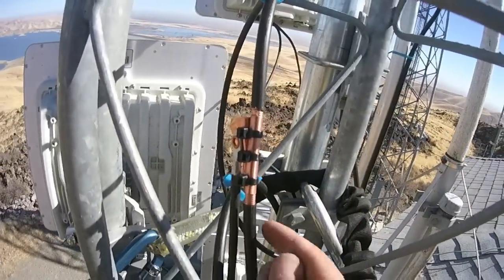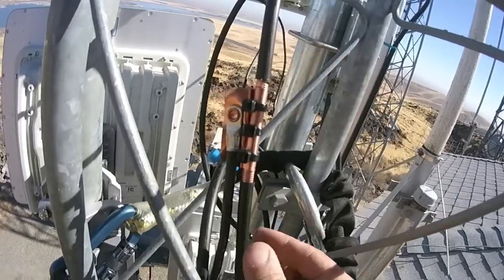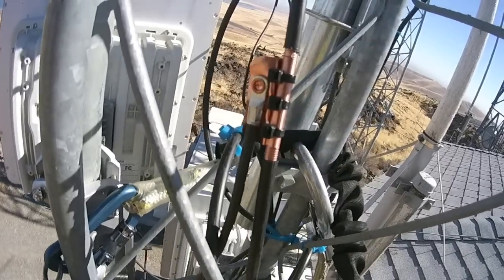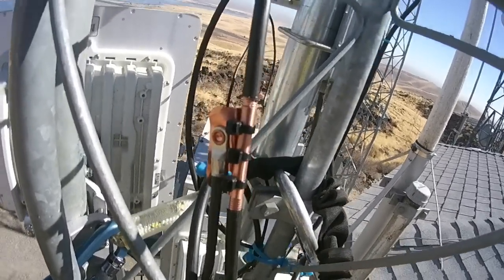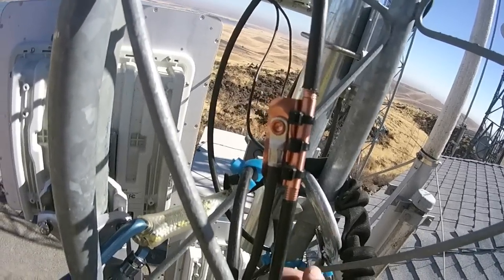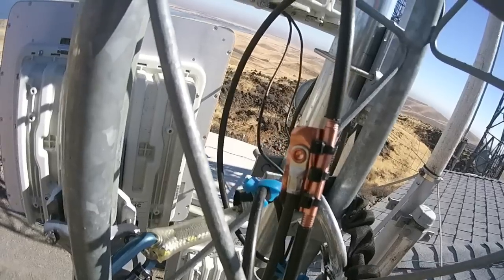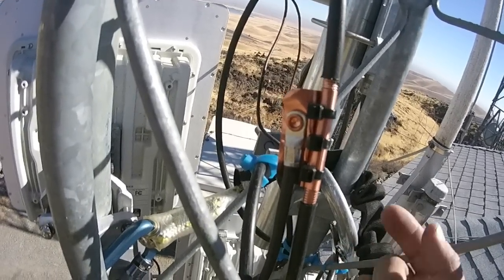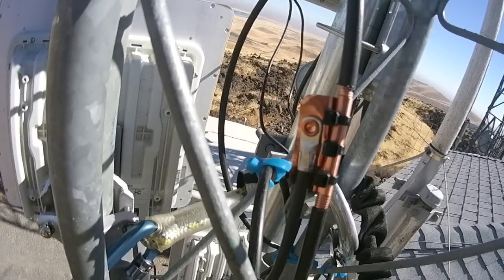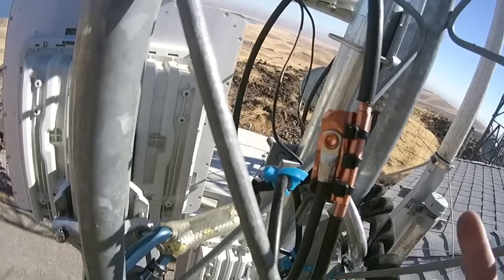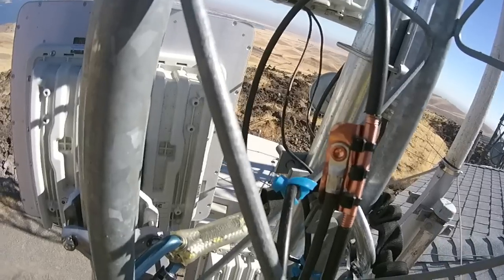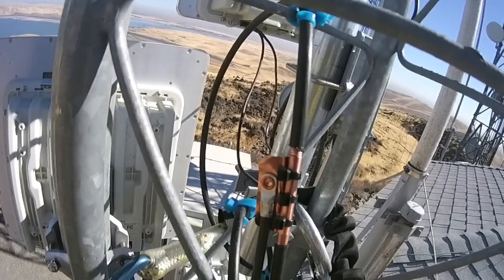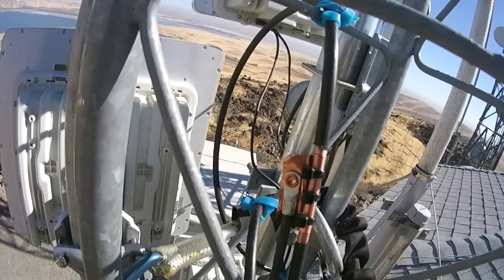So here, before I wrap it up, this is the grounding of the shield. This is like Cat 5 cable. And it's got a copper sort of shielding on the outside. And here's the ground wire that I'm supposed to attach to the tower or the system grounding system. In this case, it's just going to be grounded to the tower. And the tower is grounded to earth ground. So lightning, of course, is going to fry everything. So who am I kidding? But this is for residual sort of electricity from a lightning strike from a distance. We might get a strike, let's say, 100 yards away. But you'll have that parasitic sort of electricity in its surrounding area of the strike, energizing everything in this location here. So this is just to direct all that unwanted electricity to ground so the equipment is protected.